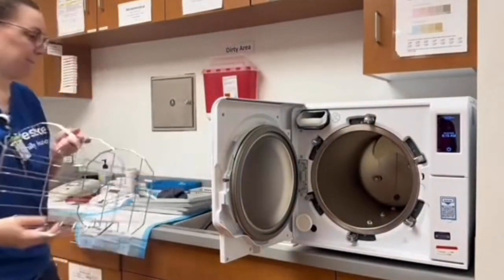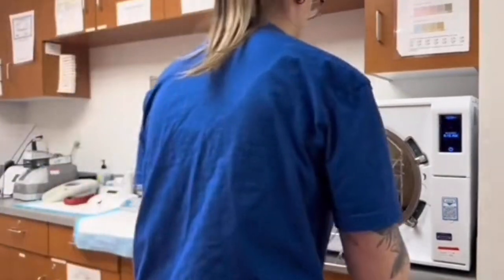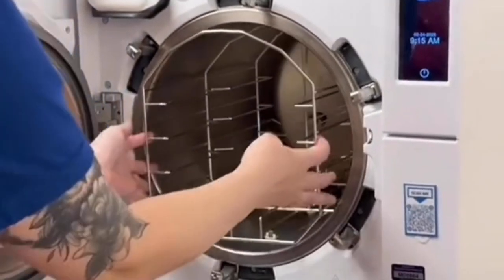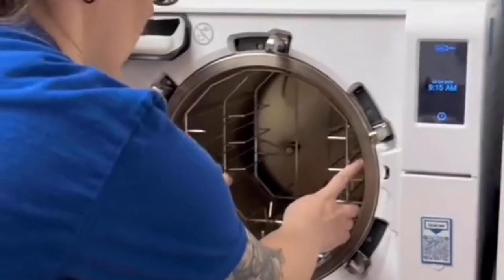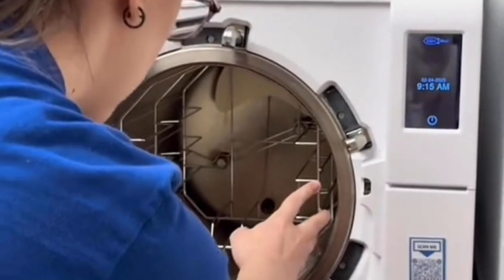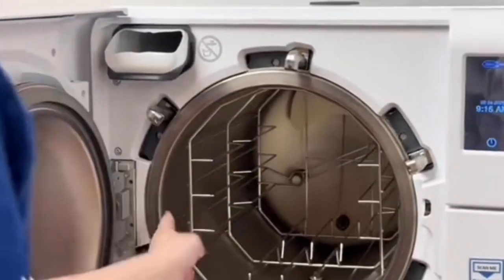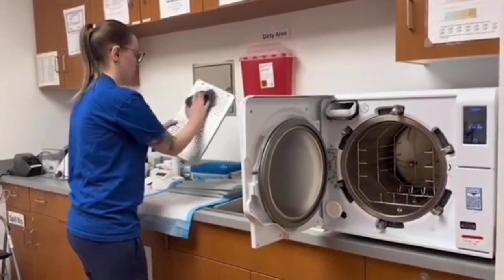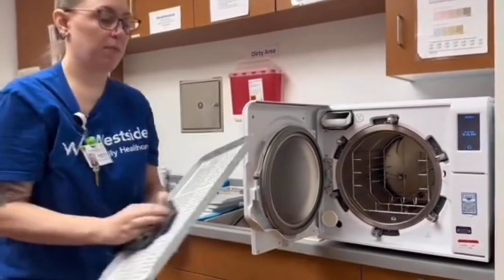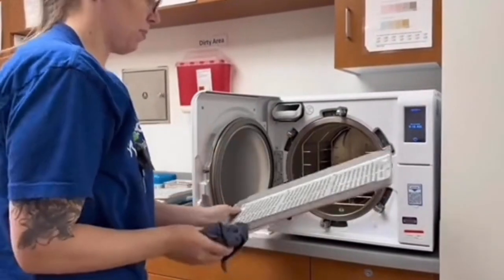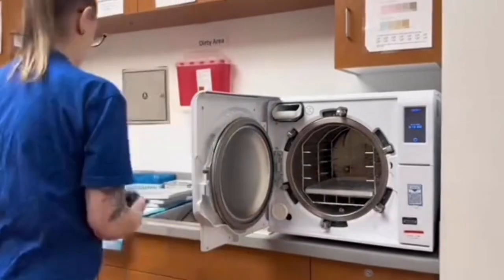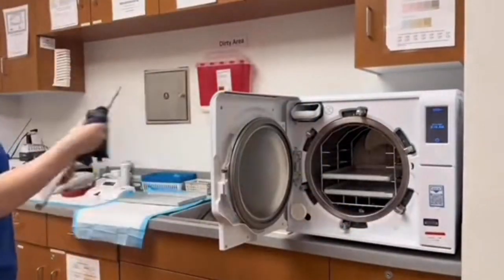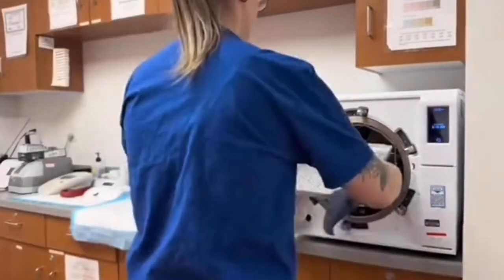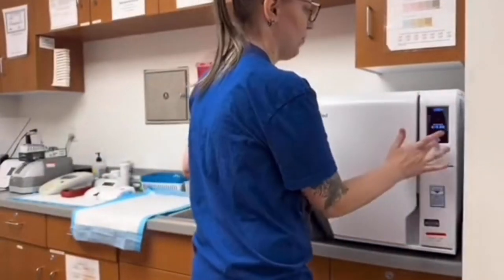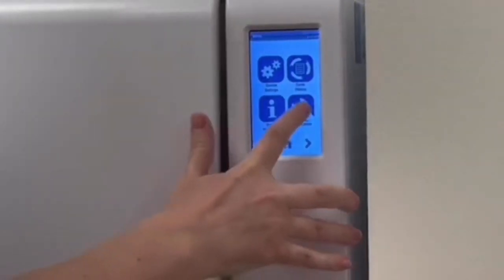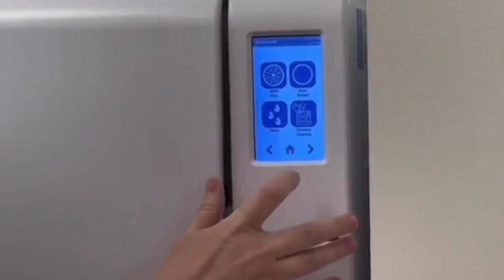To put the chamber rack back in place, be sure to align the rack so that when you push it in gently, you will hear a click. Then gently pull to confirm it is in place. Finally, wipe the trays and put them back in the rack. On the home screen, go to Maintenance and then Chamber Cleaning to reset the cycle count to 0.